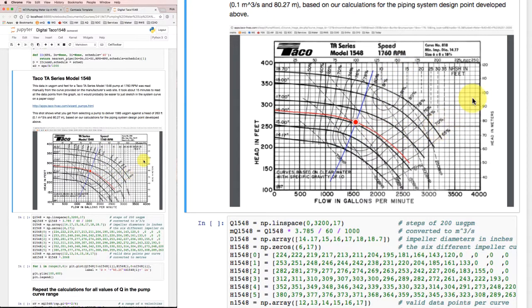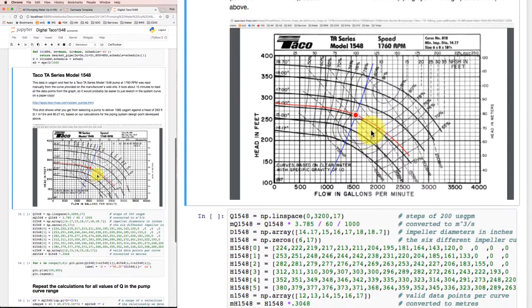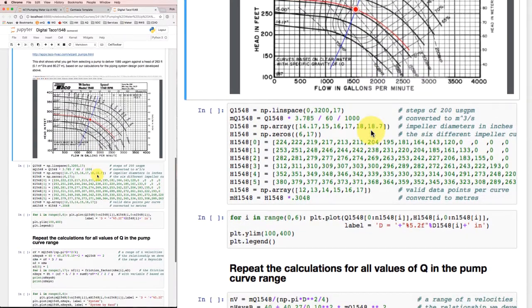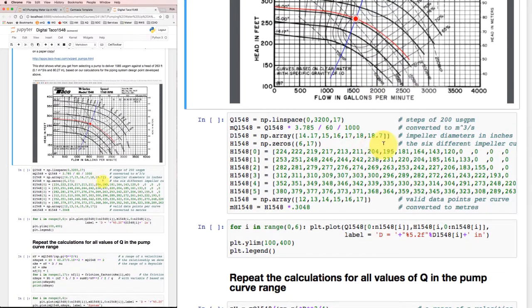Now the easiest way to do this almost always is to take this curve that you get from the manufacturer, print it out on a piece of paper and draw some data points on it with a pencil and connect them by free hand to figure out how the system is going to operate. That's what you'll do in almost all situations. Start with a paper copy of this and you can draw your pump curve on there. But in this case I've gone and digitized this information just to make our lives a little easier.